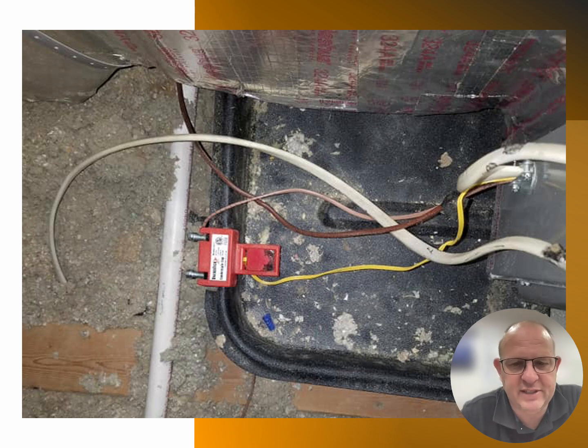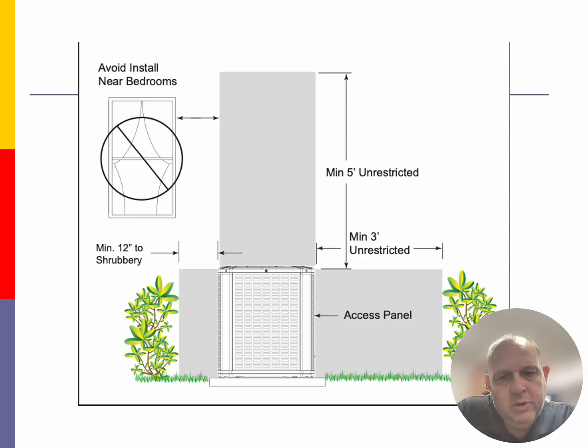So when we look at places that we want to install the outdoor unit, there are a couple of places that we want to avoid. We do not want to put an air conditioner beside the bedrooms. This is true for air conditioning. This is true for heat pumps. The noise of the unit might infiltrate into the walls, and then the occupants of that place would find the noise of the air conditioner very disturbing. The occupants will end up not enjoying the noise that the air conditioner is going to produce.